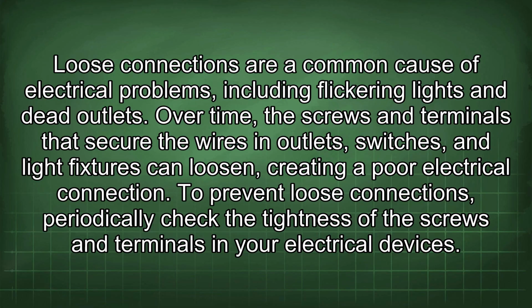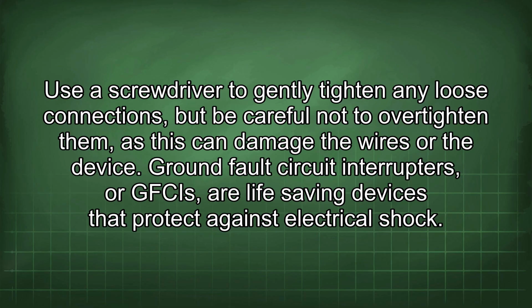Over time, the screws and terminals that secure the wires in outlets, switches, and light fixtures can loosen, creating a poor electrical connection. To prevent loose connections, periodically check the tightness of the screws and terminals in your electrical devices. Use a screwdriver to gently tighten any loose connections, but be careful not to over-tighten them, as this can damage the wires or the device.